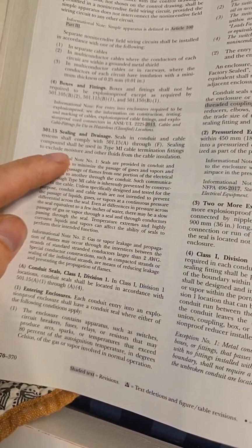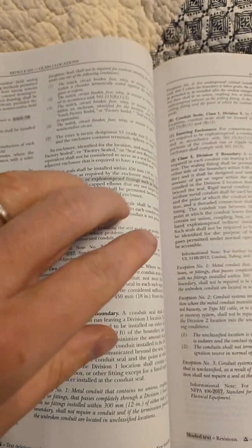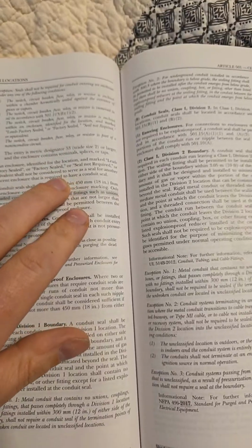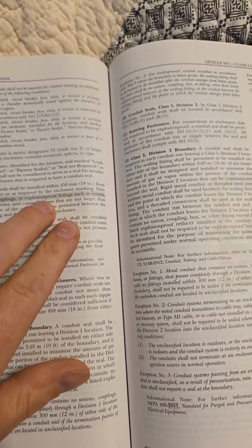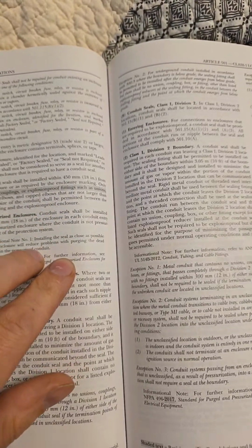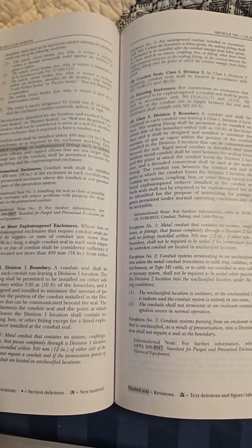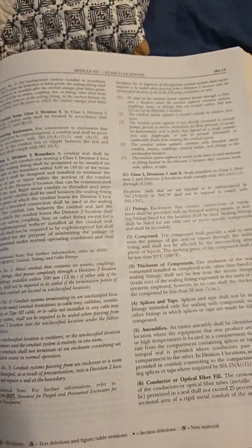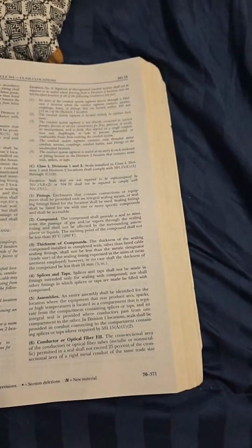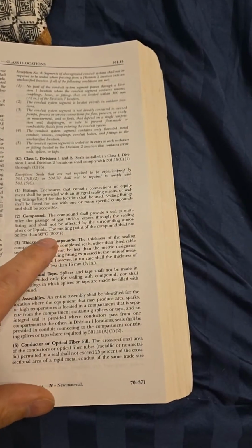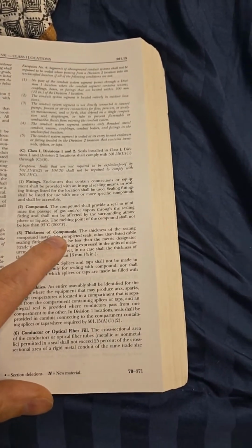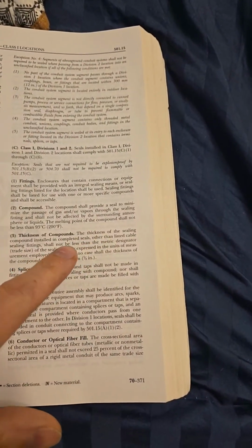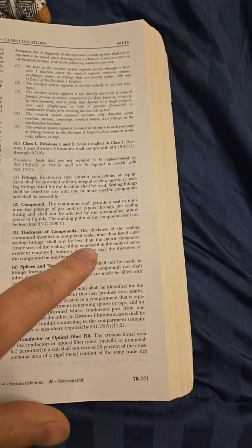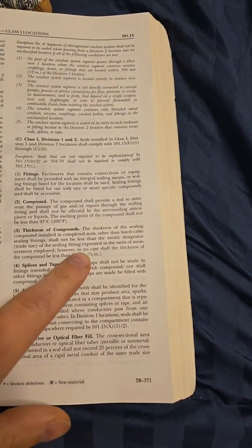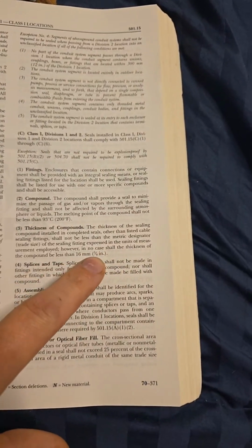I don't feel like it's going to be here though. I feel like it's going to be somewhere else. Let's look over here. The entry. Seals 18 inches from the enclosure. I think I had it in inches though. Let's see if we can find this here. How thick does the seal need to be? There's the compound. Thickness of the compound. Check that out. Thickness, installed, completed seals, listed cables shall not be less than the metric designated trade size of the sealing fitting expressed in units. In no case shall the thickness of the compound be less than 5/8 of an inch.